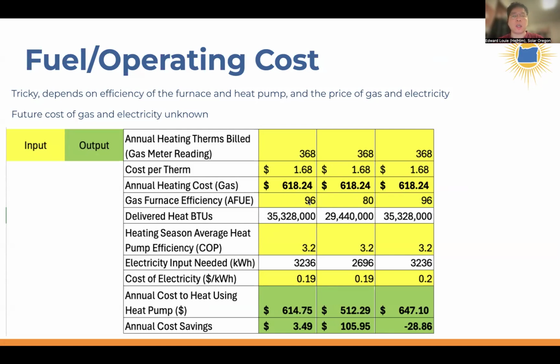then if you were to switch to a heat pump that has an average efficiency of 3.2 over the course of the winter, and the cost of electricity is 19 cents, then switching from a 96% efficient natural gas furnace to a heat pump with a COP of 3.2 at an electricity cost of 19 cents, and if your current gas cost is $1.68 a therm, you would save $3. So basically no cost difference.